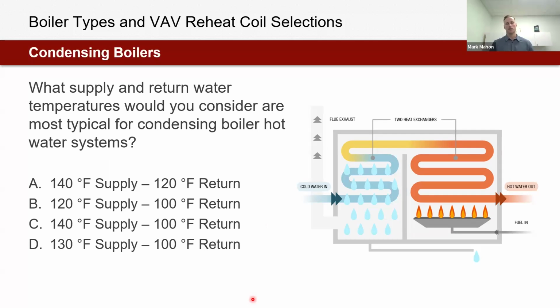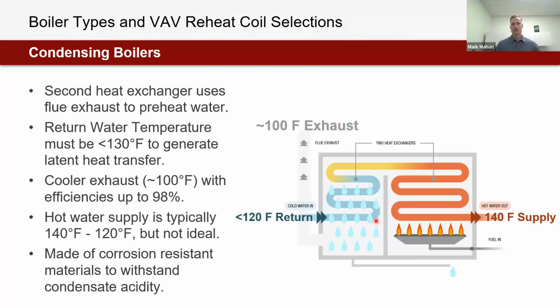And I think that makes a ton of sense because we see these systems being leveraged and used differently. Now, I will note, when I look at most schedules for single duct VAV reheat, I frequently see 140 supply and 120 return.